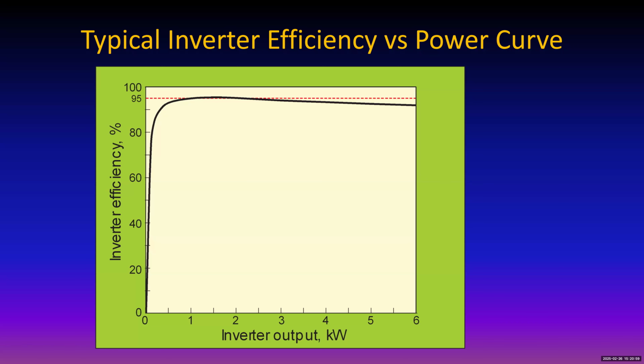And why does it drop off as you go up to higher output ratings? Well, it drops off simply because electronic components still get warm, and you have I squared R resistance losses as you start pumping out more electricity. But notice these units peak out at somewhere near, say, 20% of their maximum operating capacity. Even when they get out to maximum operating capacity, they haven't lost very much efficiency. It's at very low loads, just like the other sources, that the efficiency of the inverter goes down. All right, so it's useful to know that.